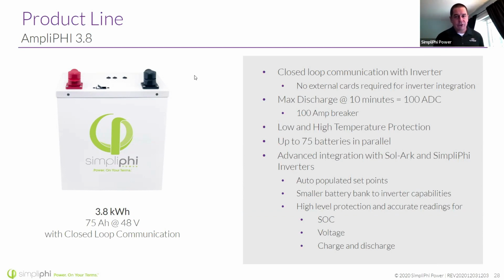Because of communications, you can parallel up to 75, which is still huge. And it makes commissioning easier because you've got some auto-populating set points. Now, there's still going to be what I call customer expectation set points, where you go in and say, okay, how far are we discharging the battery, and when does my generator start? How does the system behave? But the battery is going to tell the inverter the set points it needs to keep the battery happy.